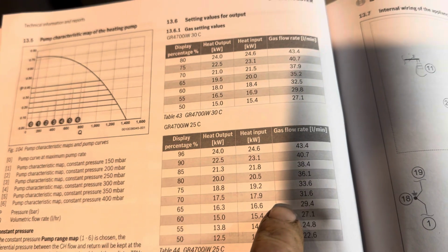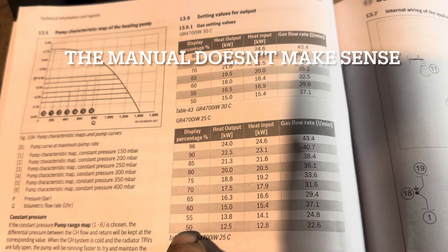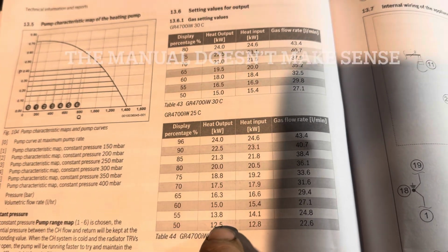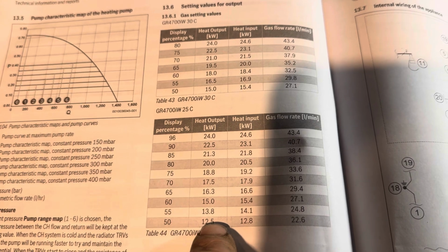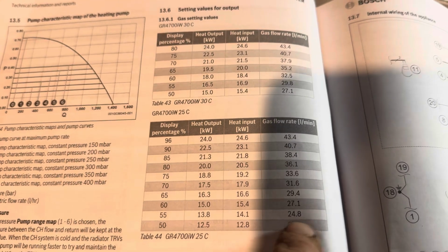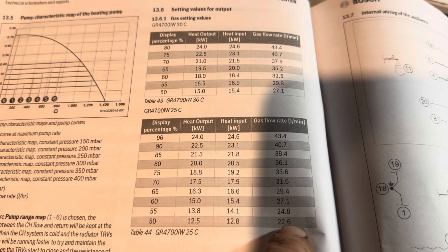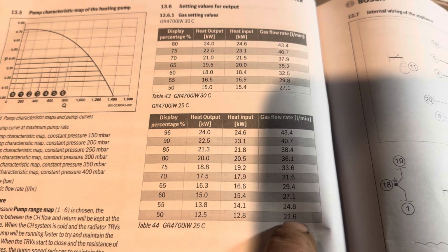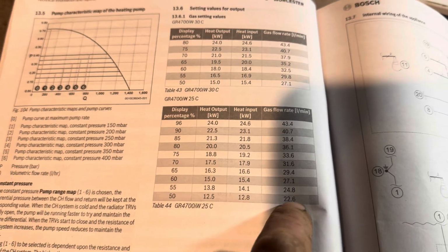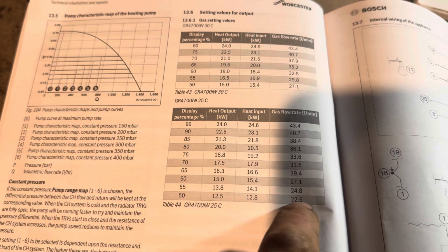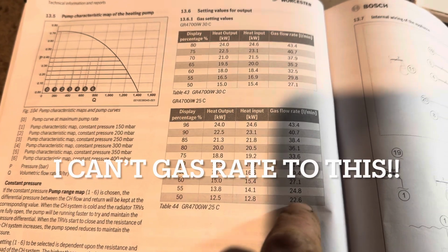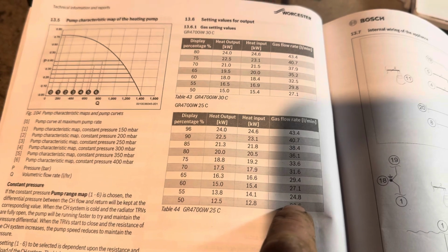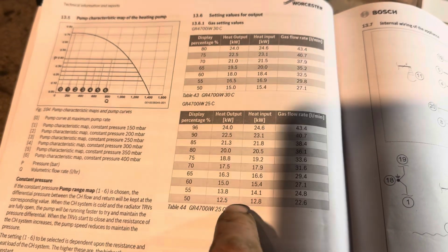on page 90, as you can see there. 50 degrees, 50%, 12.5 heat output, 12.8 input. Now we need a gas flow rate of 22.6. All I've got to do now is go down to the gas meter and check the gas flow rate, and if we get that or thereabouts, that will indicate what the heat output is going to be.